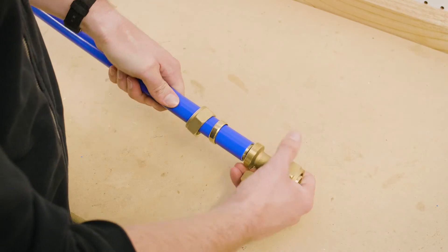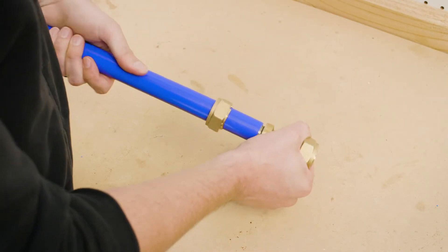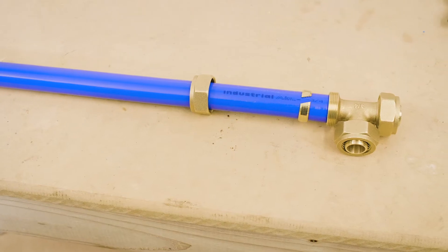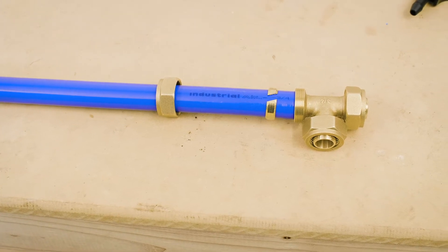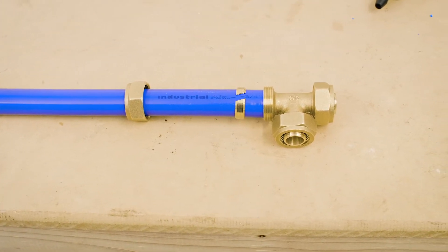Next, push the fitting onto the tube so that its shoulder is fully seated against the tube. Failing to do so can cause a leak or poorly connected assembly, which could disconnect when pressurized.